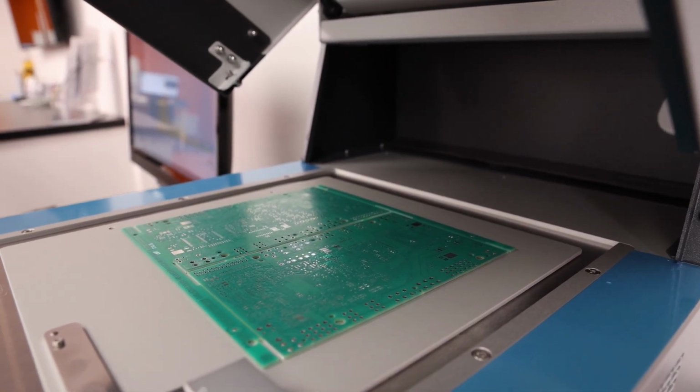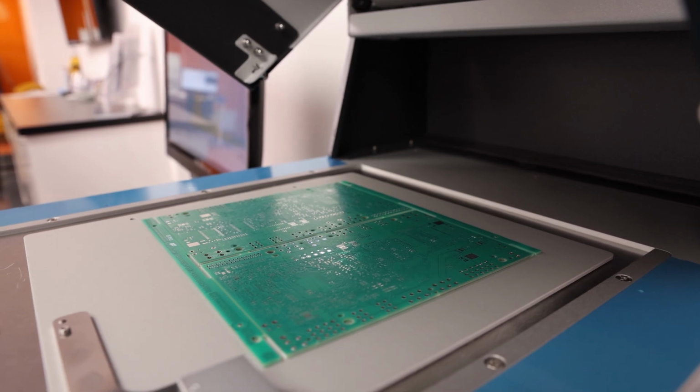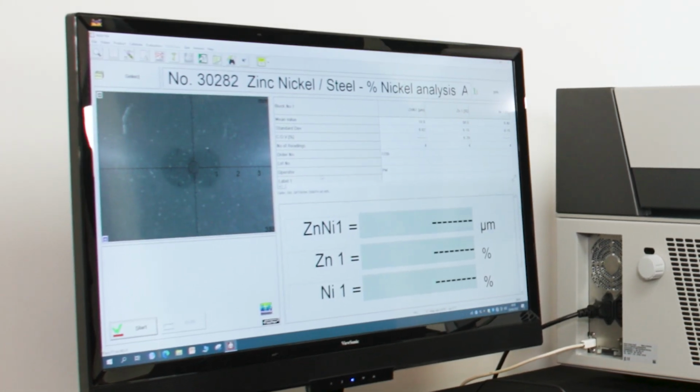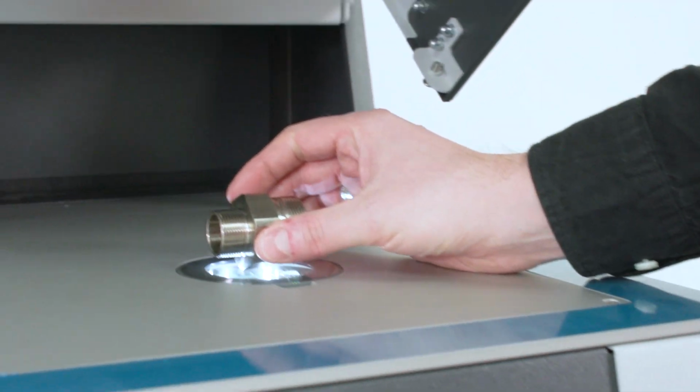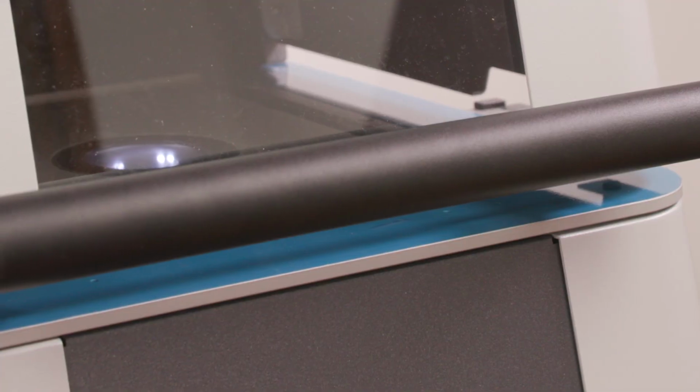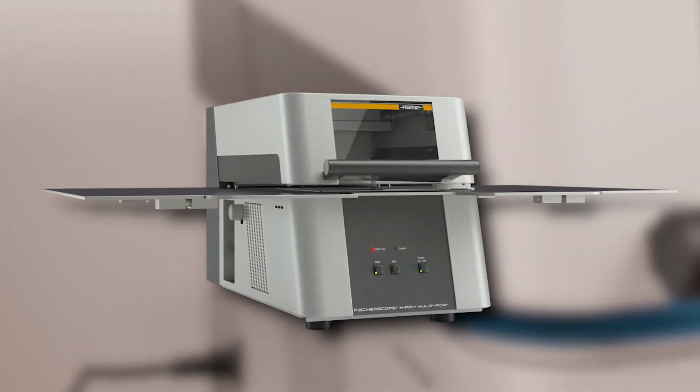The measuring chamber is large enough to measure both small and bulkier items due to its 17 cm sample height possibilities, so you can measure a range of parts and samples with just one instrument. It also has a useful C-slot gap, meaning wider shaped parts can fit across into the measuring chamber with ease.